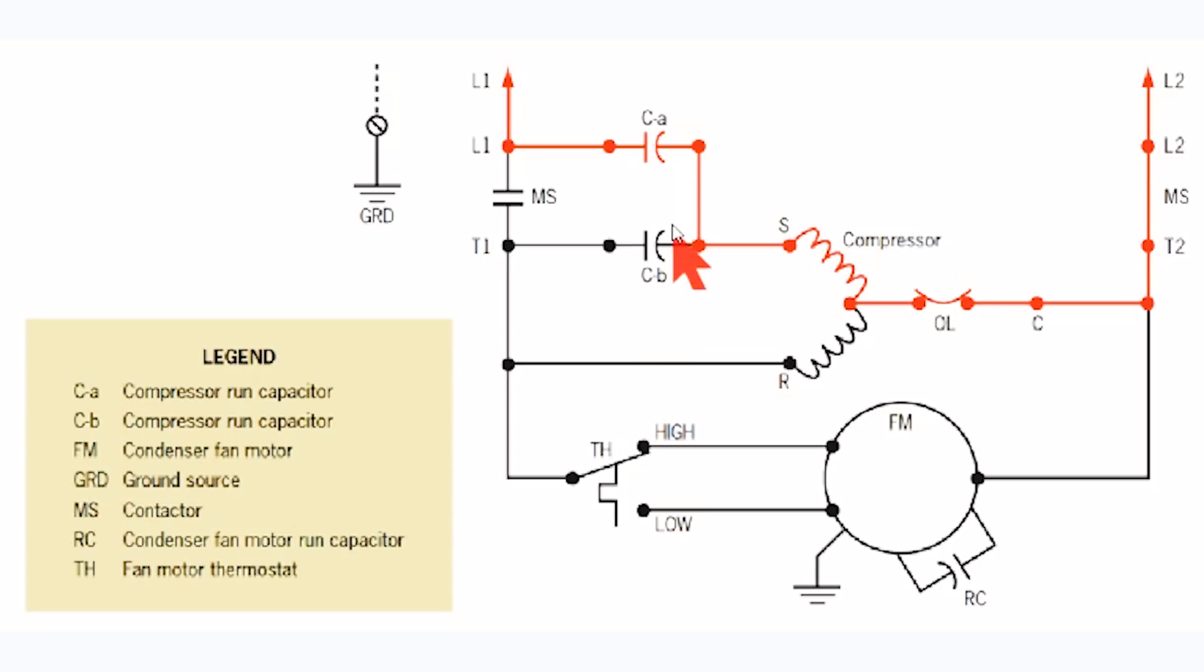But this diagram shows a setup where you have two paralleled capacitors - one connected on the load side of the contactor (MS is contactor). You have capacitor A, which is the compressor run capacitor, and capacitor B, which is also a compressor run capacitor. So they're both compressor run capacitors run in parallel, but one is fed with constant power from L1 and the other is broken through the compressor contactor.